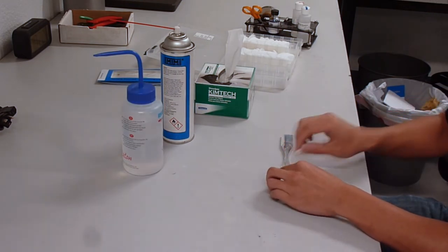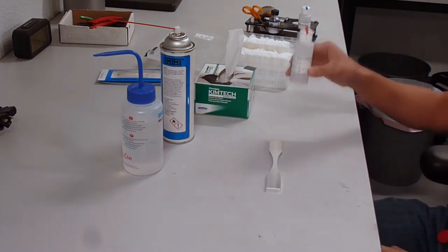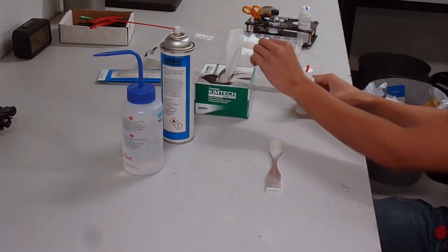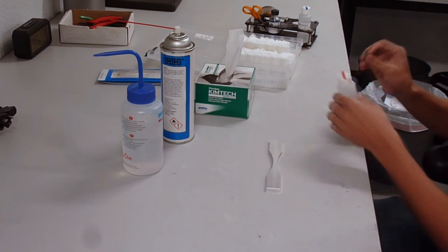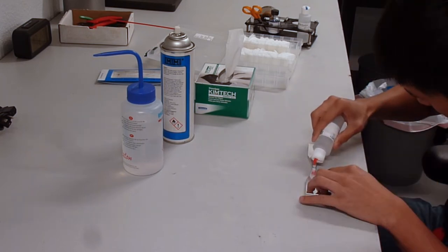This is followed by surface abrading over the strain gauge application area. If the conditioner is compatible with the test material, then abrading should be done while keeping the surface wet with a solution.